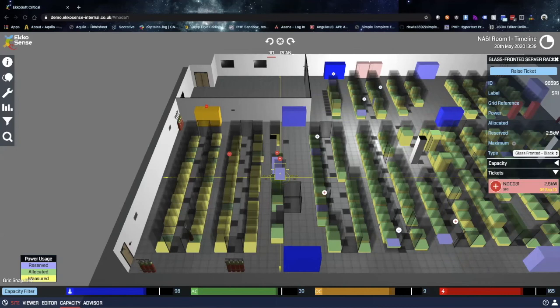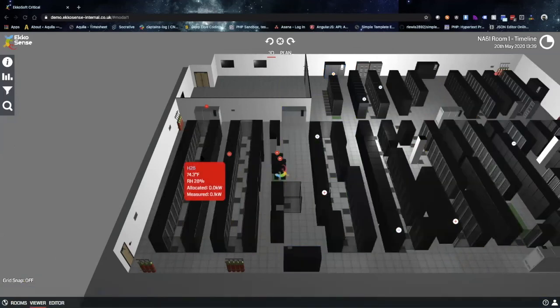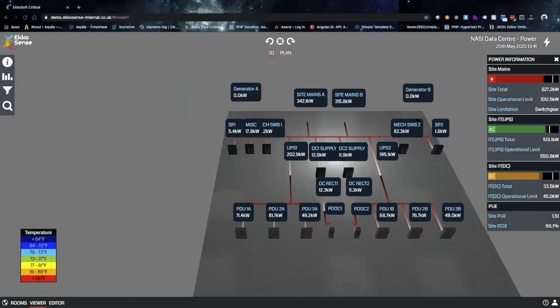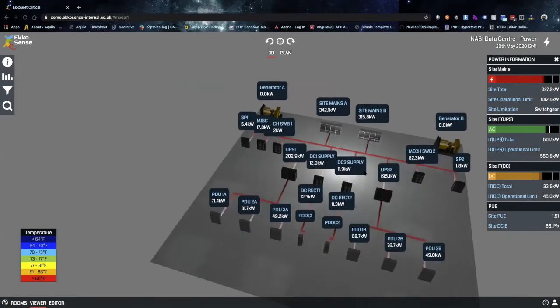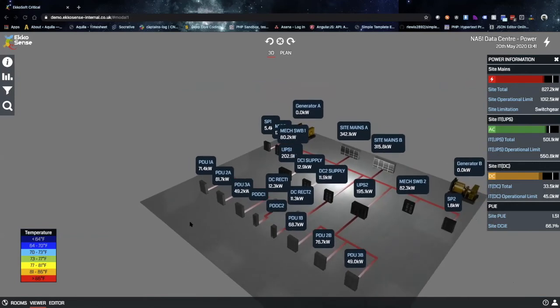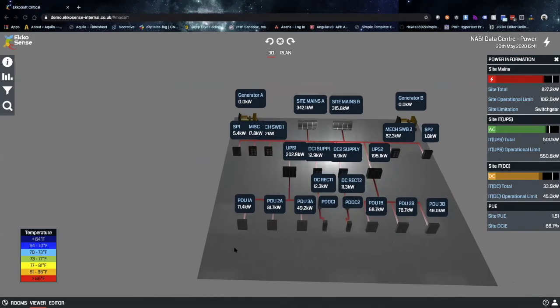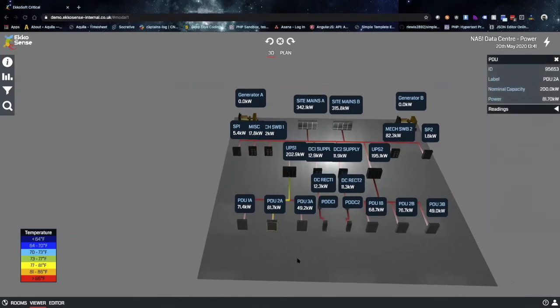From here, we can go ahead and look at the site-wide power schematic. As Lars was saying, this is much easier to see than just looking at numbers on a spreadsheet. And because it's a 3D view, we can actually turn it around and look at specific things. For example, this bottom row is room level power. If we want to see where this PDU is drawing from, all we have to do is click on it and it highlights the route that this is taking. Then we can keep moving up the chain from there and see different information. For example, total power that this UPS unit is supplying, where it's getting its draw from, different things along those lines, to make it very easy to see exactly what's going on on the power side of things.